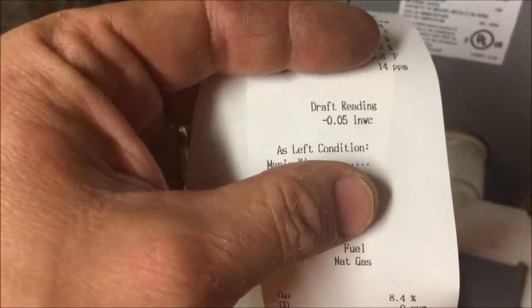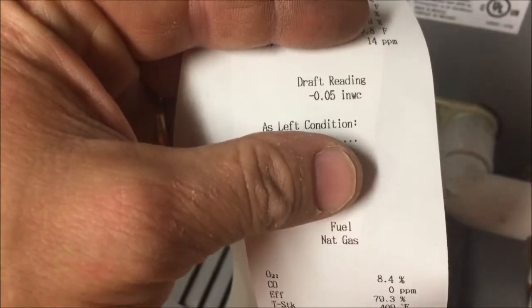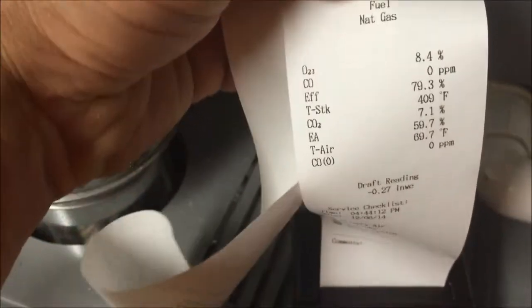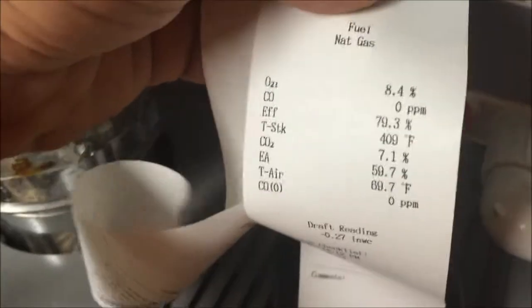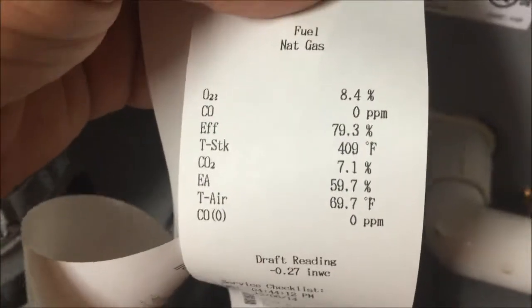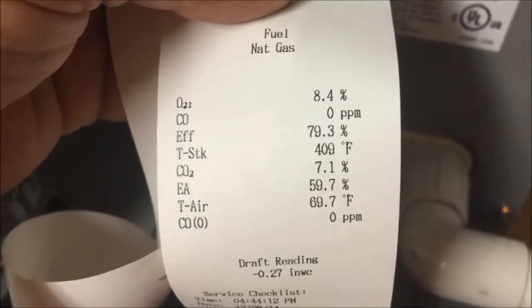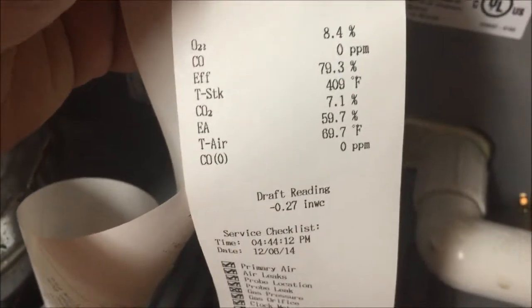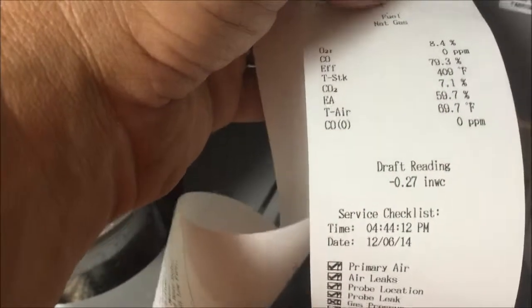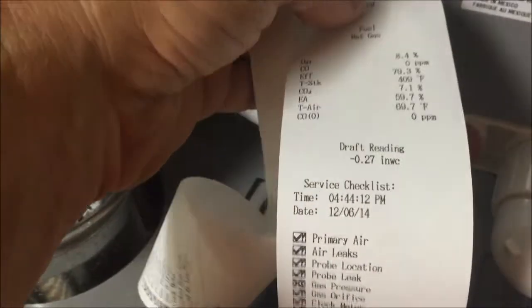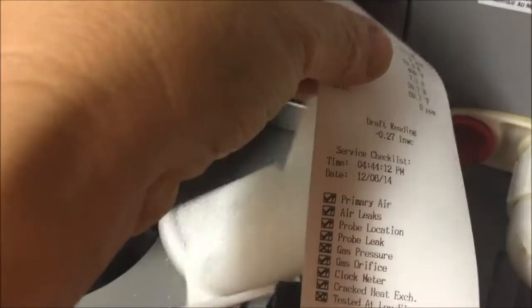Now it'll tell you your as left condition. This is when you left. This was your other reading you took. This is after you fixed everything. You've got your O2, all your readings there, your new stack temps, your parts per million. And of course the draft reading is going to be a lot different because it's a different machine.